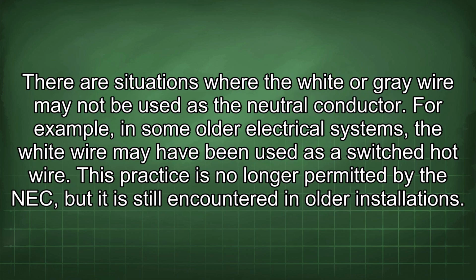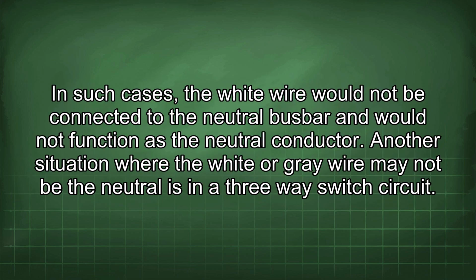There are situations where the white or gray wire may not be used as the neutral conductor. For example, in some older electrical systems, the white wire may have been used as a switched hot wire. This practice is no longer permitted by the NEC, but it is still encountered in older installations. In such cases, the white wire would not be connected to the neutral busbar and would not function as the neutral conductor.